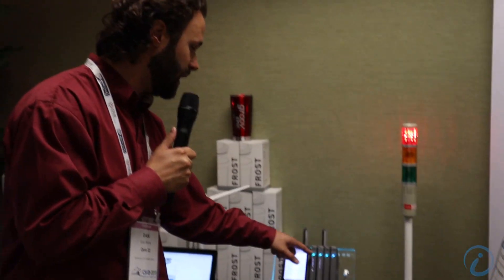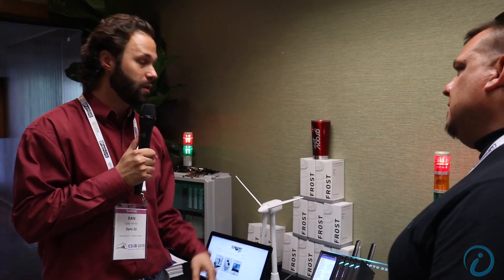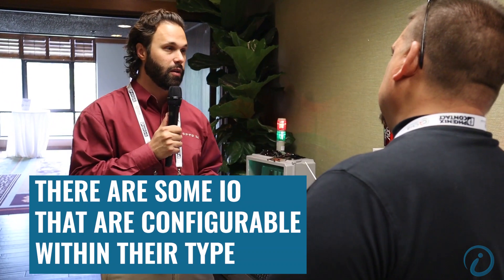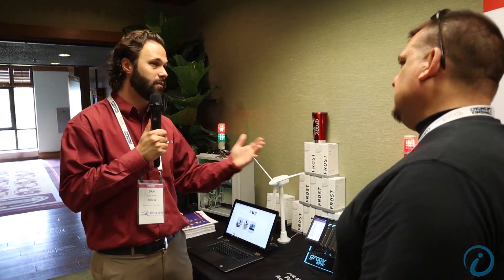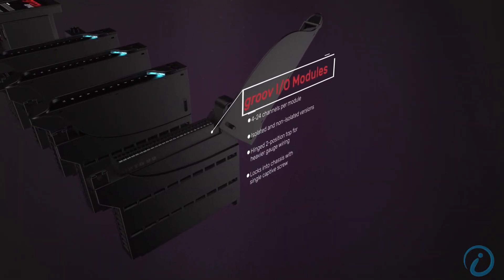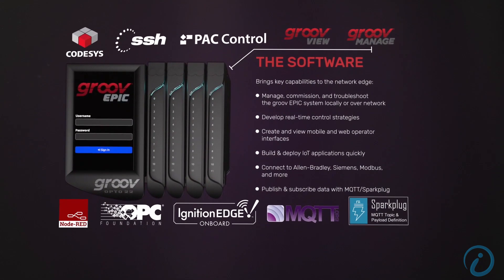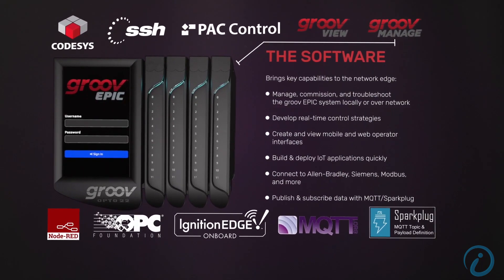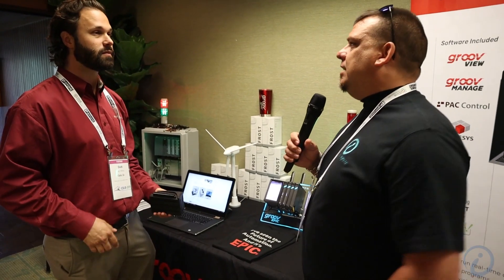The IO is configurable — each IO module is specific to its type. This module here is a DC output module, this is a DC input module, and this one is a thermocouple module. We do have further developments for IO modules that may have a mixture of types, and some are configurable within their type — for example, an analog input that can be configured as 4–20 mA, 0–10V, or voltage.